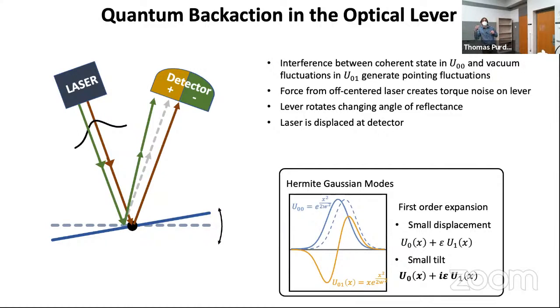That's what we mean when we say quantum limited pointing fluctuations of a laser. The vacuum fluctuations of a 0-1 Hermite-Gauss mode are interfering with the coherently occupied fundamental Gaussian mode and effectively making our beam look like it jiggles back and forth. That puts a lever arm on our force, allows us to put a torque on our mechanical resonator, makes it jiggle about. That's the back action from our measurement. And of course, when it jiggles, the lever rotates, and that changes the angle of reflection, and that shows up as extra noise on our detector. So that's back action in the optical lever.